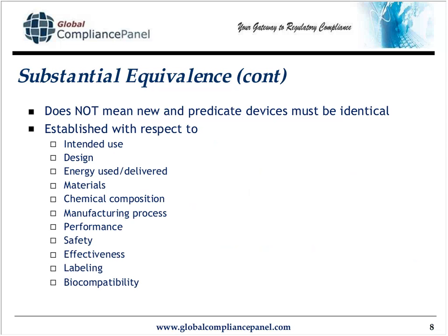If you're writing a 510K and using a competitor's product as your predicate device, you might not know their manufacturing process. But if you're using your own device as the predicate device, you do know the manufacturing process. So any or all of these that can be used should be used.